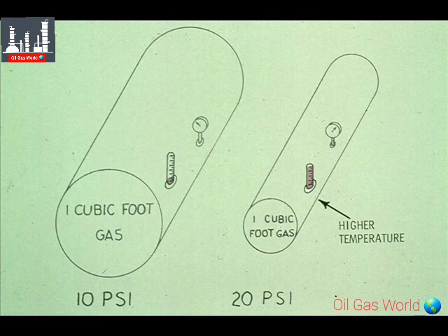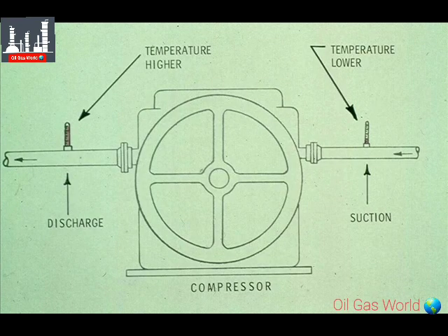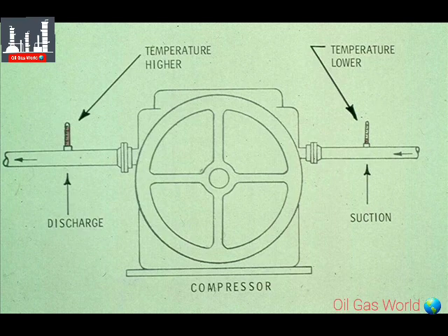Here's something else to keep in mind in regard to compressors. Compressing the air or gas in this cylinder increases the temperature of the gas. This means that the air or gas will be much hotter when it is discharged from the compressor than when it was sucked in through the intake. This often results in damage to the discharge valves from constant overheating. We'll talk more about that later in this module.